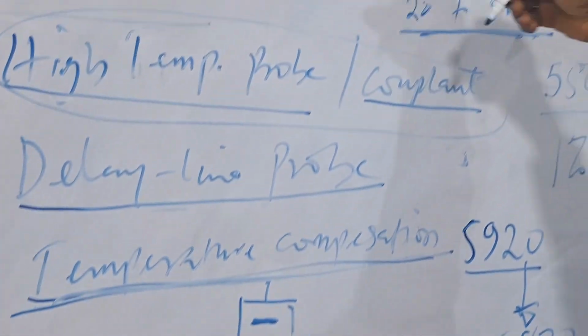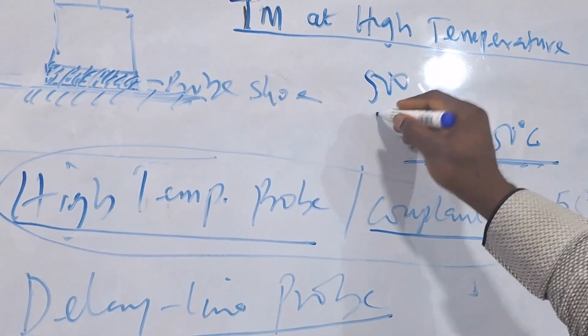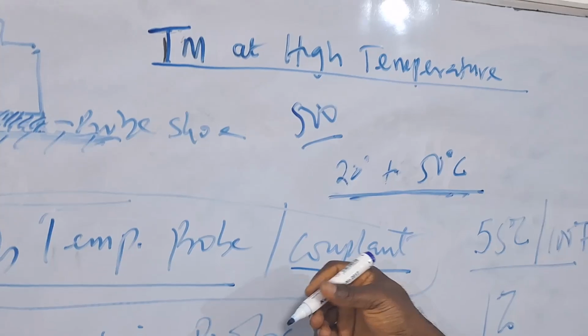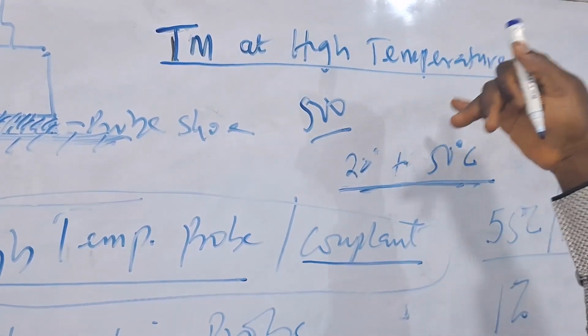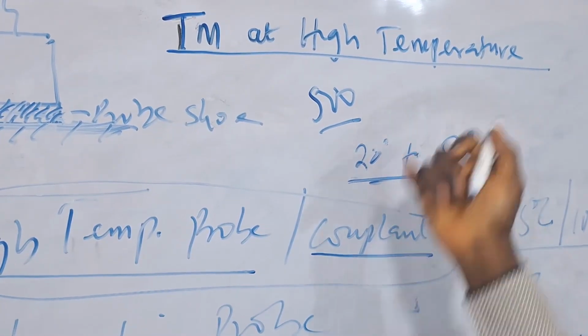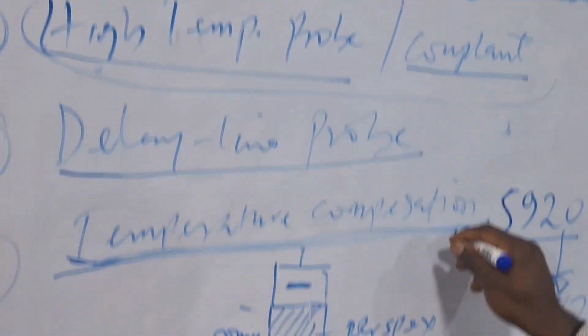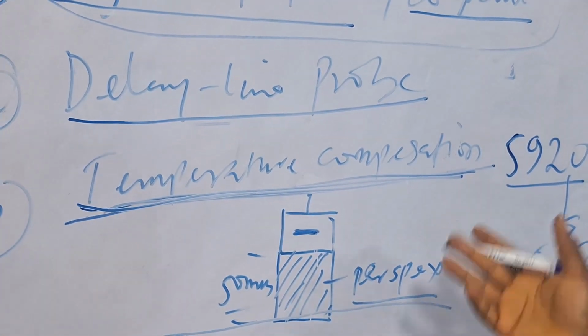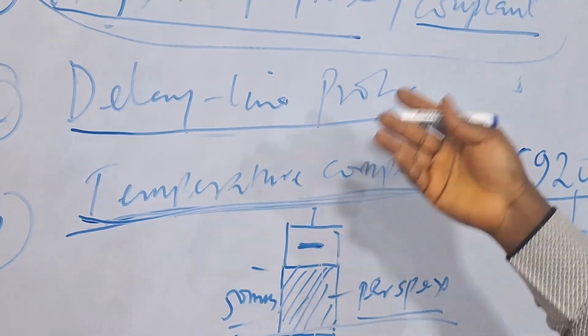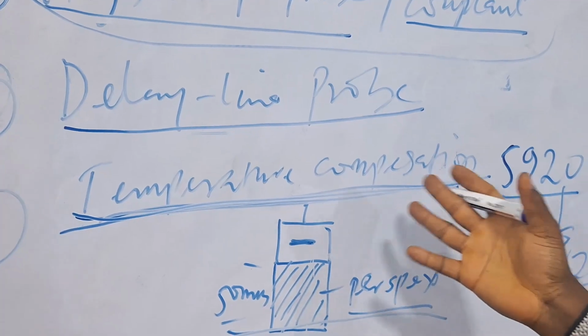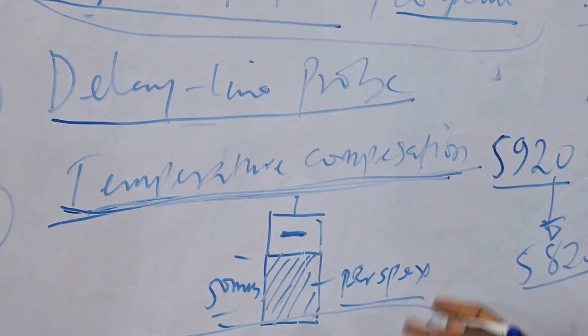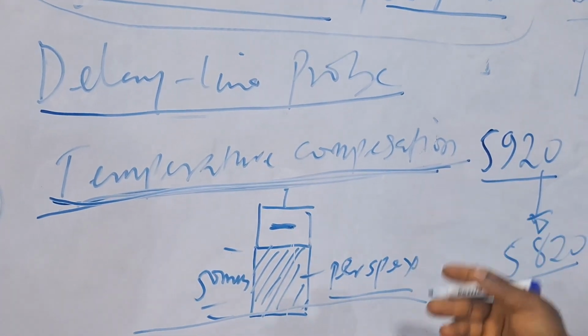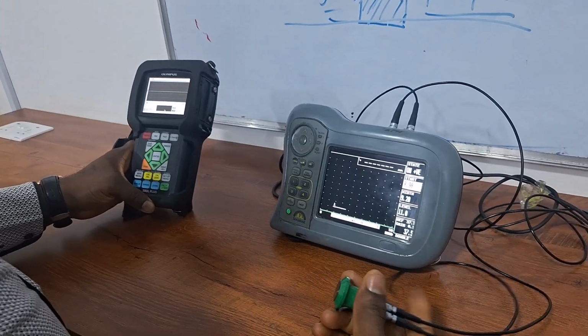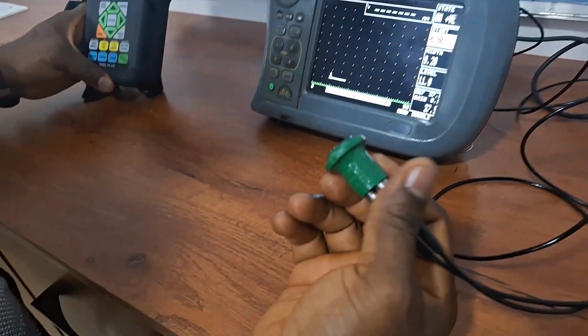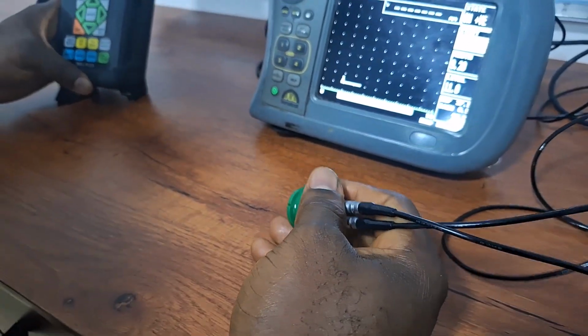But in case where you are going to have very high temperature that is going to affect your probe, you still have to change your probe to a high temperature probe while also performing your temperature compensation. So practically look at it, how to do temperature compensation and to get the accurate reading due to temperature change. We'll now illustrate this temperature compensation concept.